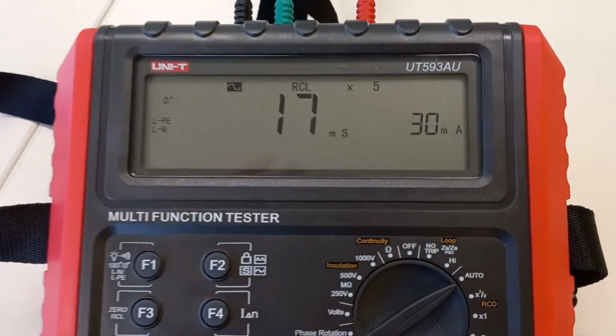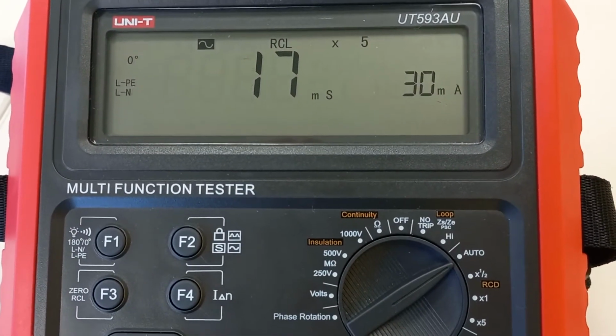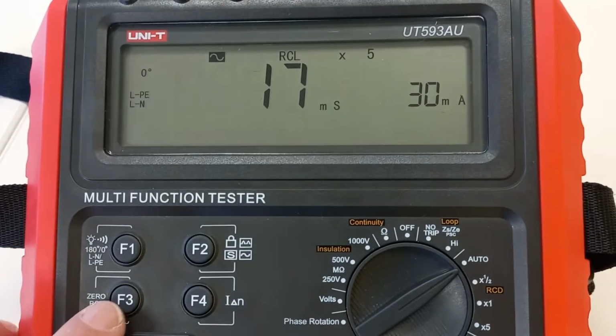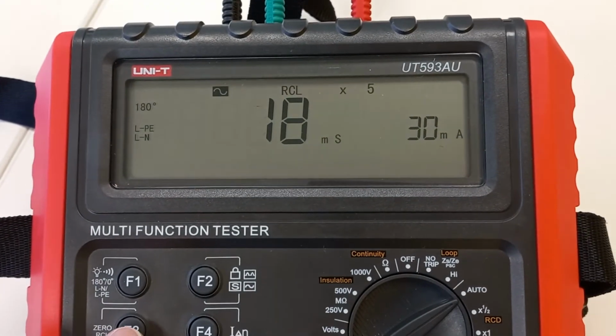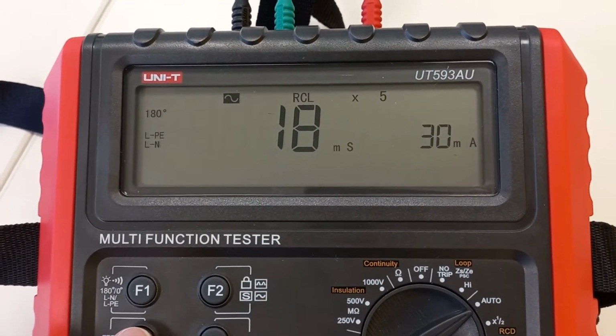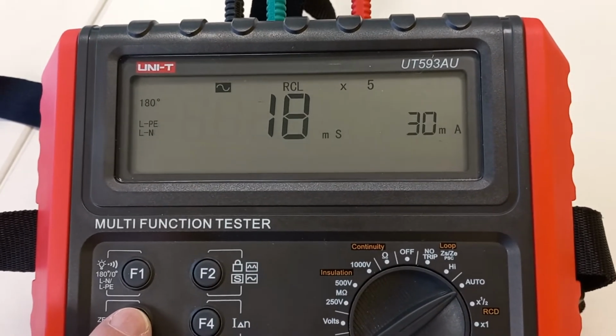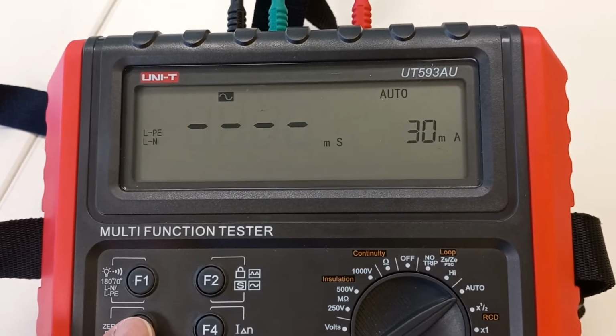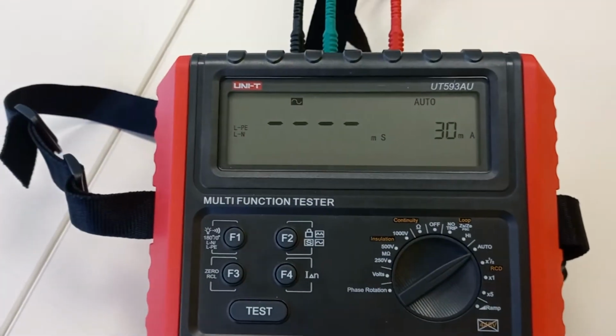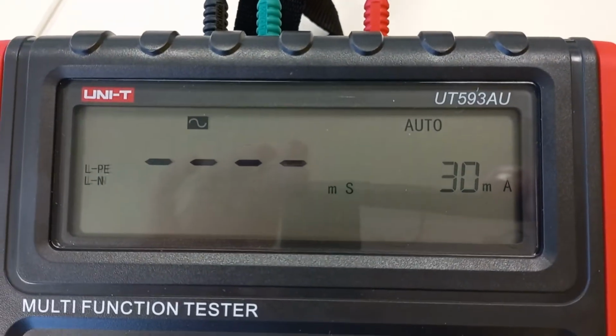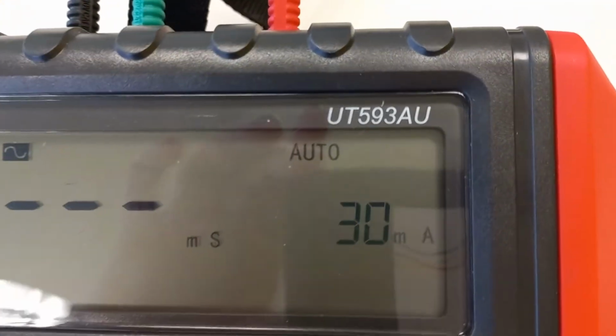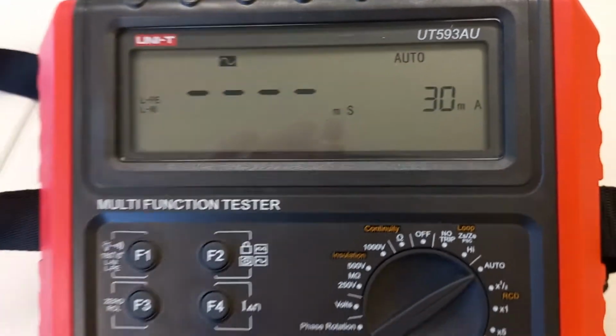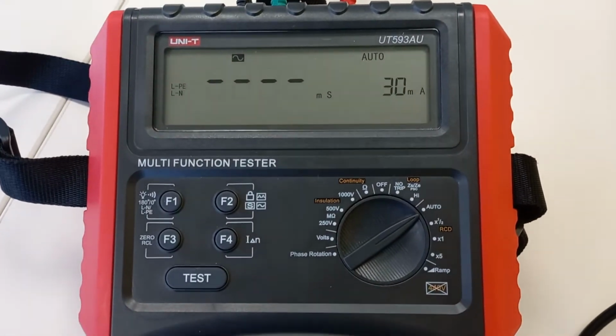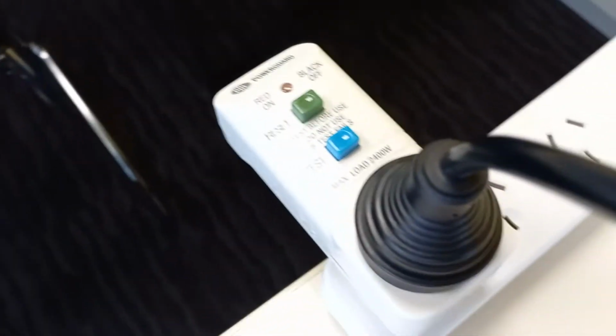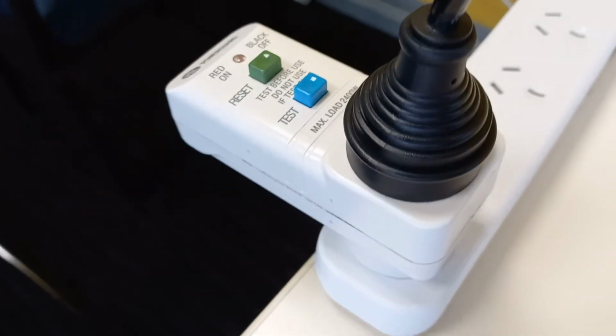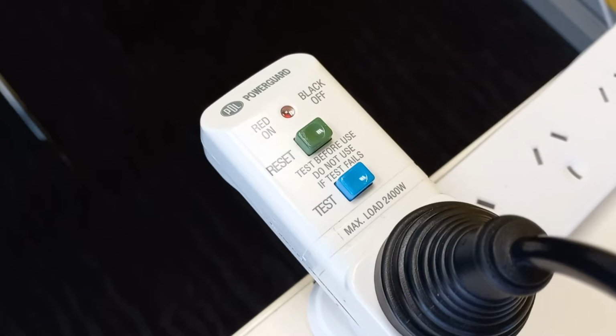At ×5, we have to trip within 40 milliseconds. It tripped out at 17 milliseconds at 0 degrees, and at 180 degrees, 18 milliseconds. So that is also well within the 40 milliseconds permitted. So that is using the UniT multifunction tester model UT593AU for testing the safe operation of a 30 milliamp leakage sensitivity portable RCD, residual current device.